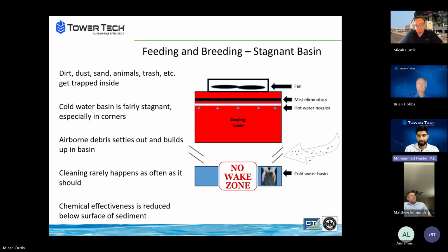Yeah, so anytime you have a stagnant water basin on a conventional cooling tower, and your water flow is not an active flow design, and your water starts pooling up in areas and not moving around, you're going to essentially be creating an environment which is very conducive to bacteria growth. And that's not only from the fact that the actual water in the basin is starting to warm up. But it's also from the fact that in those stagnant zones, you start having a collection of dust, sand, organic particles, which is all, you know, areas that Legionella bacteria is actually feeding on, right? So you have this nutrient-rich zone in a stagnant zone, which the bacteria then finds its way to, and then starts to proliferate a lot faster than you would want it to. So that's a direct result of stagnation.